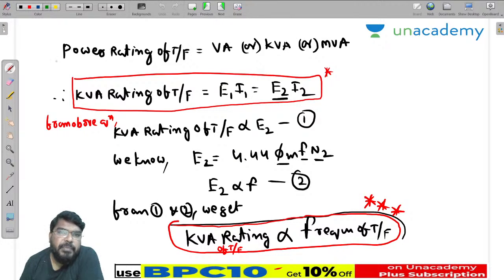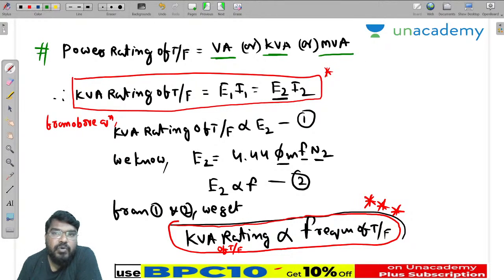Now from the questioning point of view, the power rating of the transformer is always measured in volt amperes, kilovolt amperes or megavolt amperes, but not in kilowatts. From this equation we conclude the kVA rating of the transformer is directly proportional to the induced EMF, where induced EMF is directly proportional to the frequency. So from equations 1 and 2, the kVA rating of the transformer is directly proportional to the frequency of the transformer. Is that clear now? Any more questions?